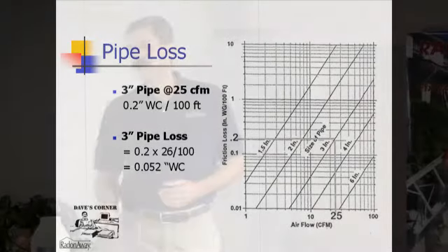inches water column. And so we can then take that information and look at various other airflows, in this case within the range of 20 to 80 cubic feet per minute, which is really where residentially radon systems operate.